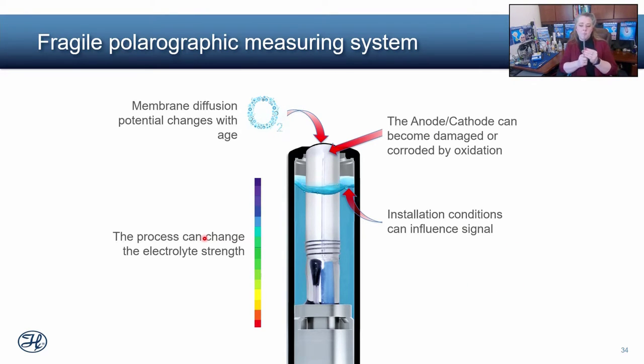Also, the installation can really influence the signal. These are filled with liquid. You need liquid to fill through everything in order to get a closed circuit. If you put polarographic probes upside down, you end up with an air gap where the platinum is. And that means you cannot have a complete circuit with your redox reaction. And so these probes can never actually measure upside down. In fact, you need them to be at least 15 degrees off the horizontal, they can't be straight either because there's too much of an air gap. You need at least 15 degrees off the horizontal to get reliable measurements.